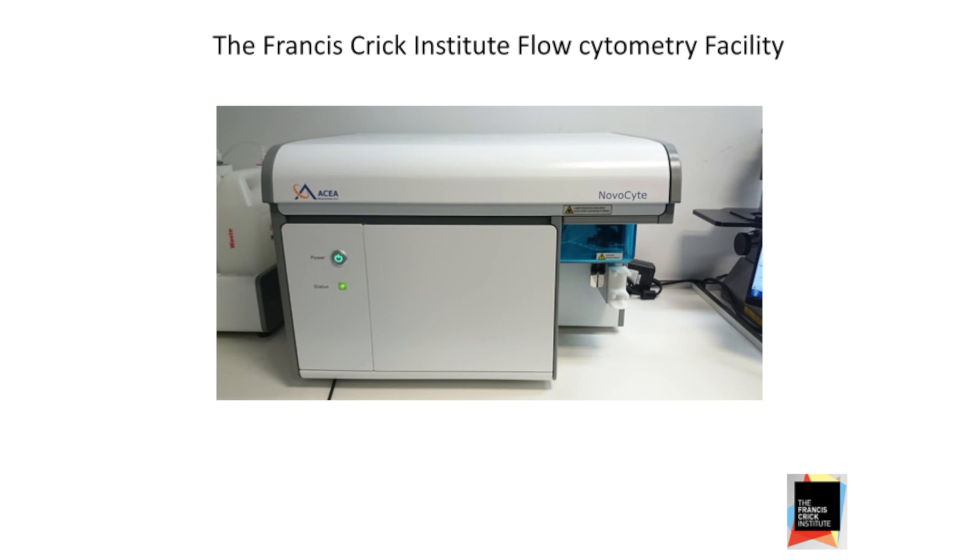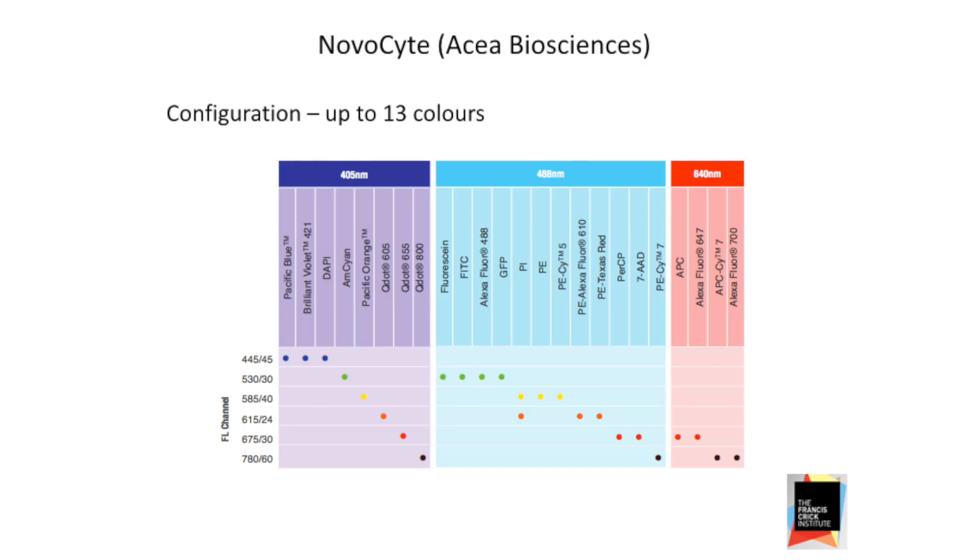Let's put it through its paces and see what it can do. I'm not going to talk too much about the machine — you can go and see that on the booth. I'm not a product manager for ACEA. But as you're probably aware, it's a 13-color instrument: six colors from a violet laser, five from a blue, and two from a red laser.